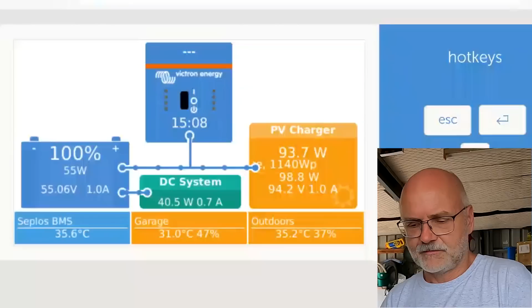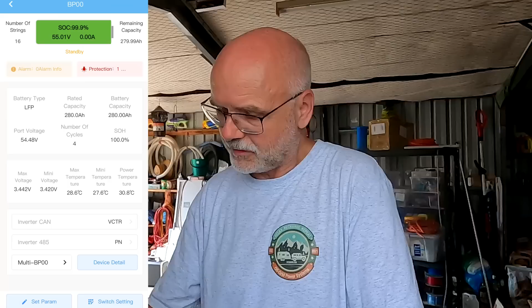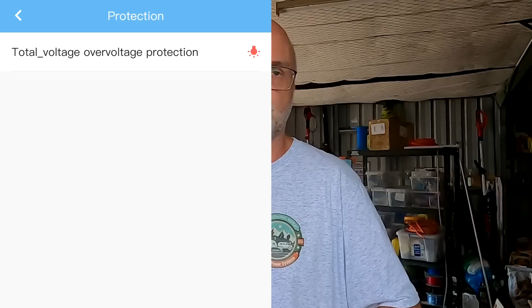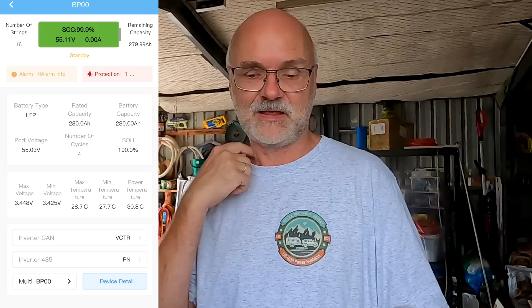And we can see here on the remote console, we are charging with around 100 watts now into the system. This power goes into the slave battery at the moment, because if we have a look at the master BMS, we can see a protection status up here. It says total voltage over voltage protection.